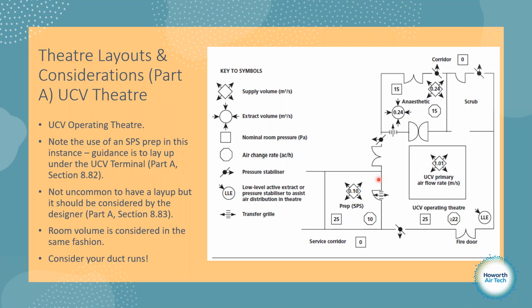And where we previously had a PRV, or a pressure stabiliser in the wall, we now have a transfer grill. And notice that the pressure is now 25 in both rooms. So what that means is we have an equalised pressure across this door. The reason it looks like that is because the Royal College of Orthopaedic Surgeons say that sterile pack stores should store the equipment, and it should be taken through and opened under the footprint of the UCV.